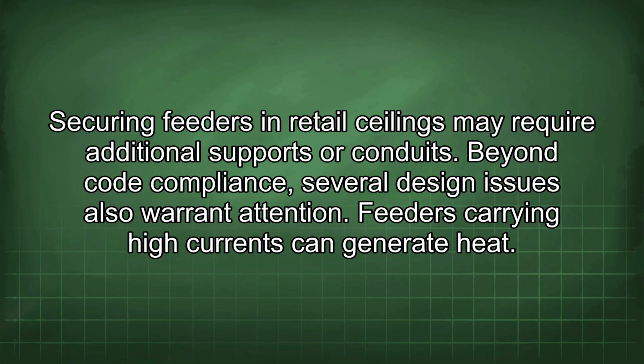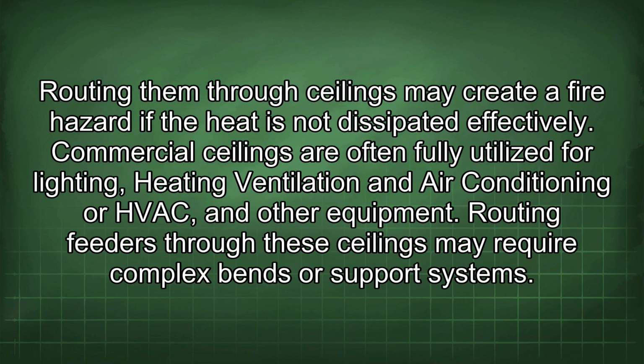Beyond code compliance, several design issues also warrant attention. Feeders carrying high currents can generate heat. Routing them through ceilings may create a fire hazard if the heat is not dissipated effectively. Commercial ceilings are often fully utilized for lighting, heating, ventilation, and air conditioning, or HVAC, and other equipment. Routing feeders through these ceilings may require complex bends or support systems.